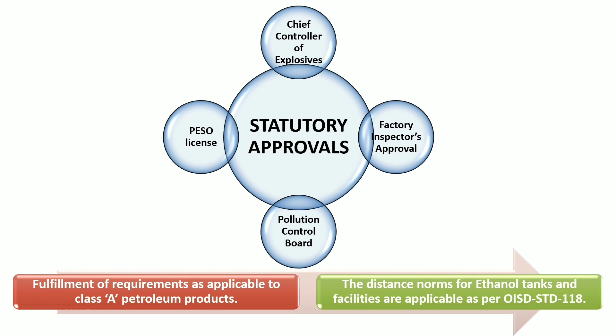The most suitable equipment for Zone 0 is intrinsically safe equipment. However, Zone 1 should have electrical installations of explosion-proof or flame-proof type. Equipment featuring enhanced safety is also good for these environments. All automation and process equipment installed near Zone 0 and Zone 1 should have a power rating of lower than 24 volts. Fixed type leakage detectors, such as hydrocarbon detectors designed to detect vapors of ethanol, are required to be installed near handling facilities like tank farms, pump houses and automated loading or unloading stations.